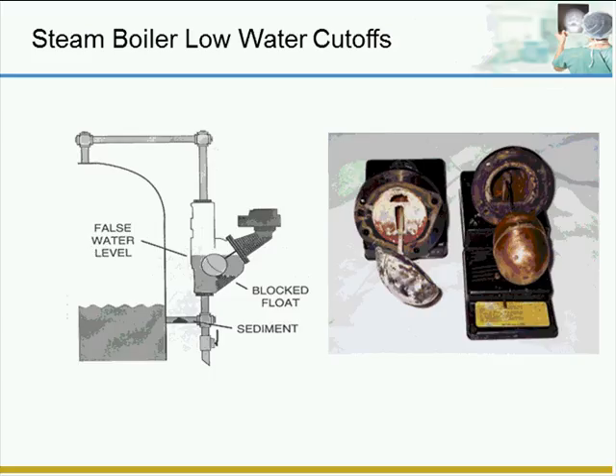This picture here, the picture to the left, shows a fully assembled low water cutoff. It's a cross-sectional view. As you can see, the water level in what's supposed to be the boiler is lower than the float assembly. The float is actually being blocked by debris. You have sediment also in the line, which is not allowing the water level to drop. These are a few cases where the low water cutoff will not operate properly and can result in a failure of the boiler. To the right, we have a cavitated low water cutoff float. Somehow the boiler became vacuum and cavitated the float.